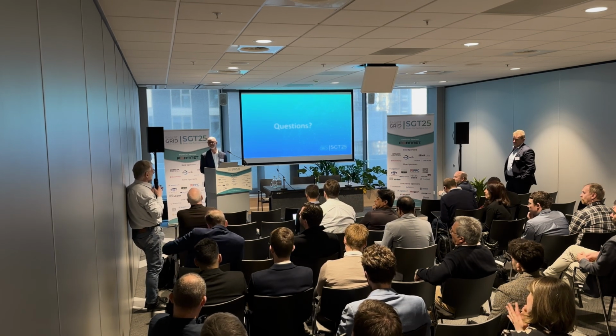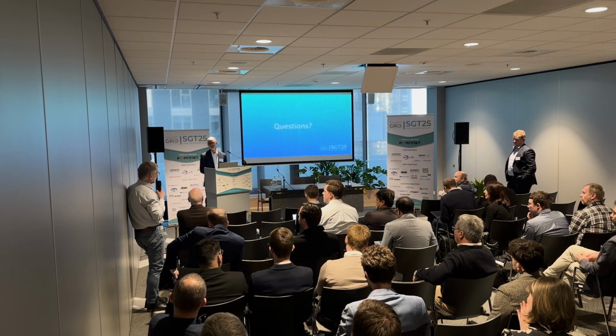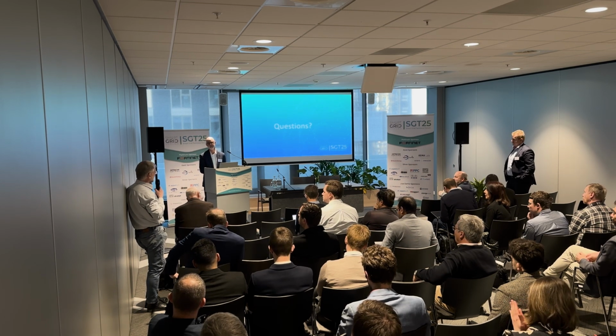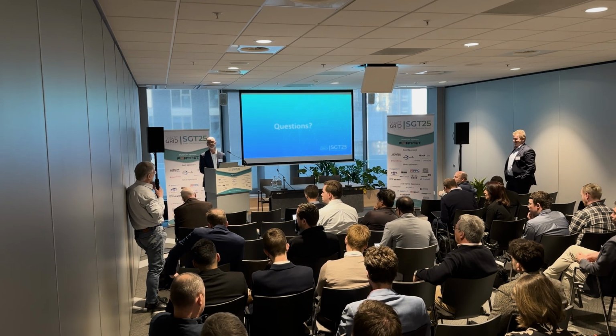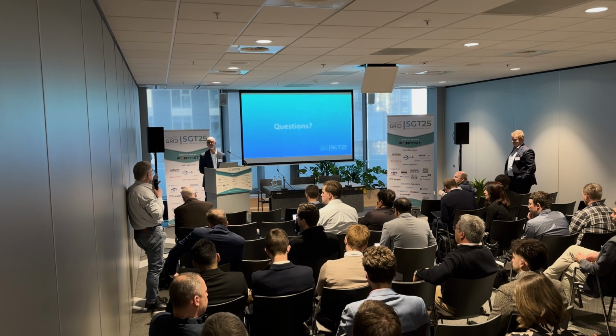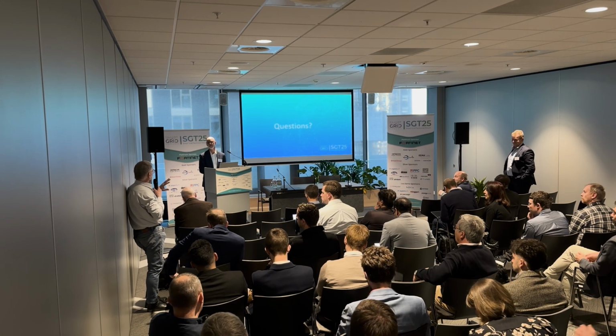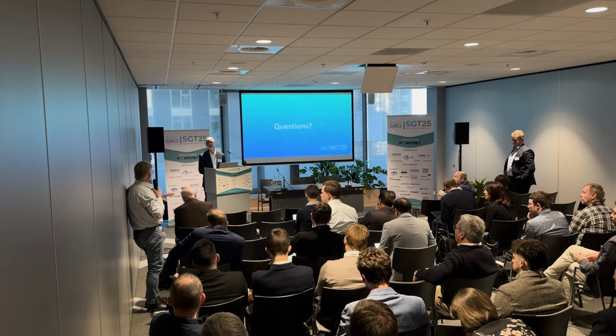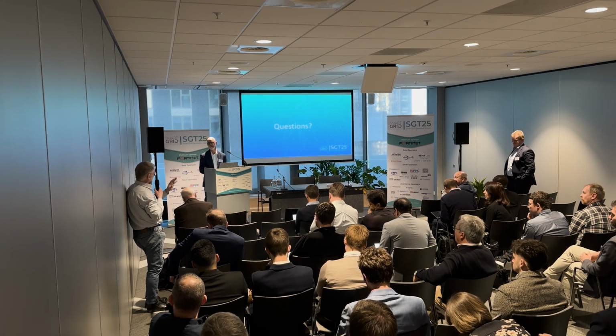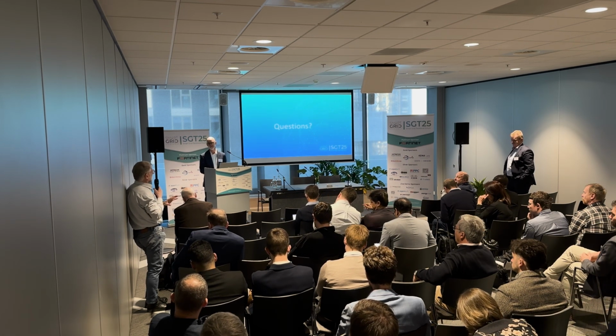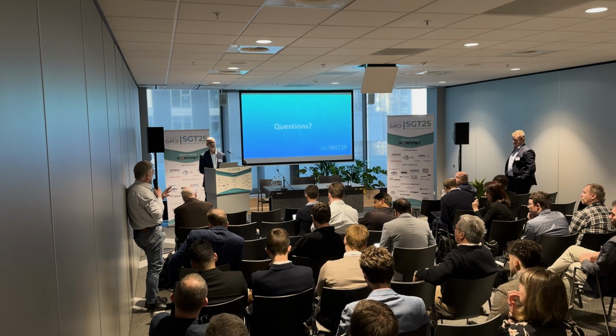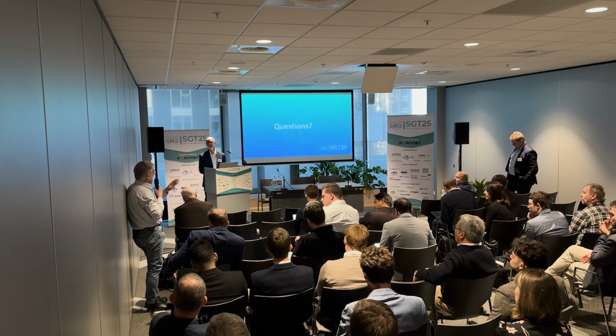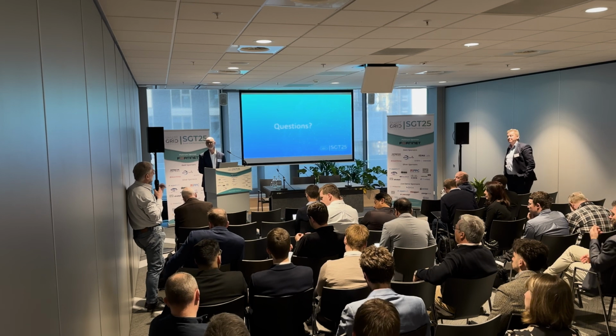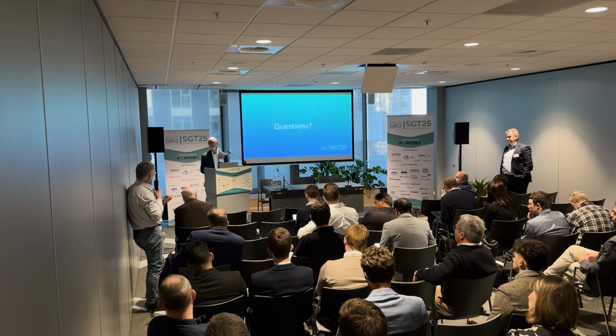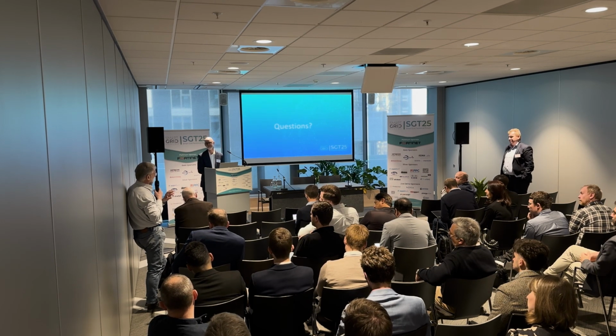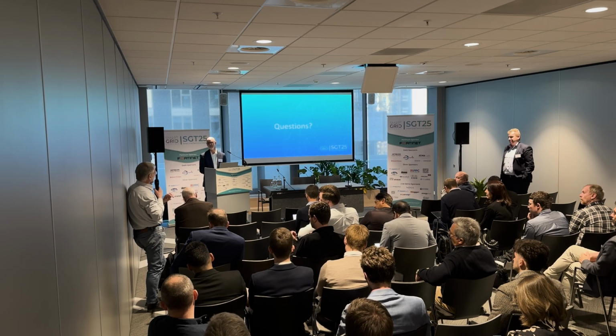Which means everybody's Modbus is different, everybody's MQTT is different, which is a configuration nightmare. And when I look at the other things you've mentioned, we've got DNP3, 104, very flat measurement structures. 61850 goes into a particular way of structuring it. They're not always compatible. There are moves ahead to have OPC UA with a mapping to 61850—I hope that will be coming out at the end of this year.